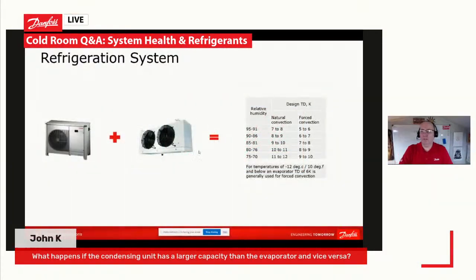So that should be coming up on the screen. If we think of a nice, simple cold room refrigeration system, we've got our condenser unit, our cooler, and the match between those two. Let's say that's 10 kilowatt and that's 10 kilowatt, that's matched, and at that match we'll have a particular temperature difference, and that will give us, as we've said before, our humidity on our cold room. So we've got our humidity levels there, and our design TD, our temperature difference between evaporating and air onto the cooler at a specific delta T.